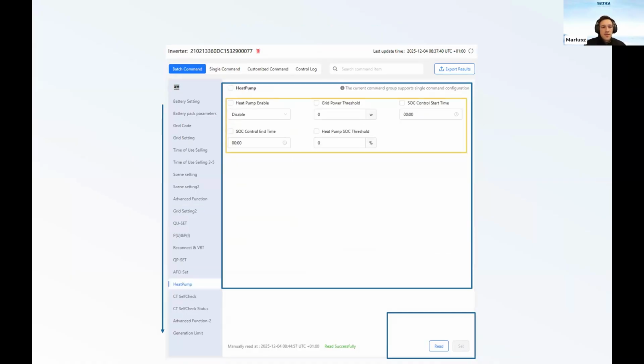And I think it's the second-to-last setting, for the heat pump. We can set up the grid power threshold, so how much electricity we push into the grid before we turn on the contactor, and also the SOC control start time and end time. For example, if we see that in the morning from 2 a.m. to 4 a.m. we still have 80% of the battery, we can force the heat pump to discharge it and use this energy before we charge from the grid or from the PV modules, because the sun will rise.